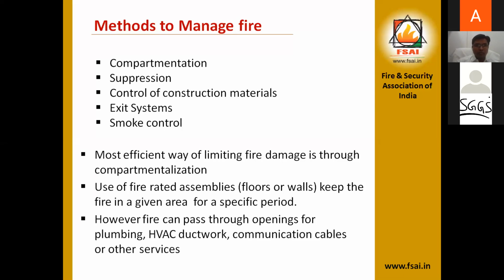The most efficient way of limiting fire damage is through compartmentation. Use fire-rated assemblies like floors or walls to keep the fire in the given area itself for a specific period so that people get a chance to evacuate or move from that place. However, fire can pass through openings for plumbing, HVAC ductwork, communication cables or other services.